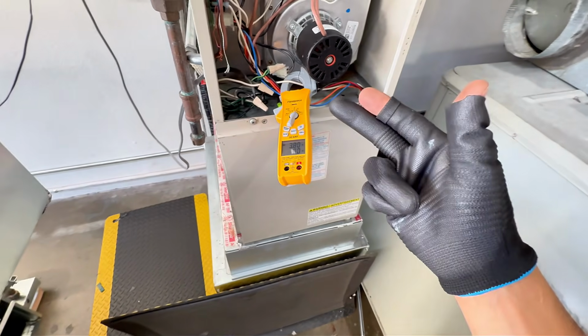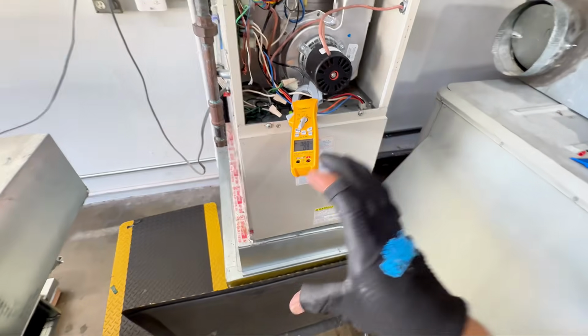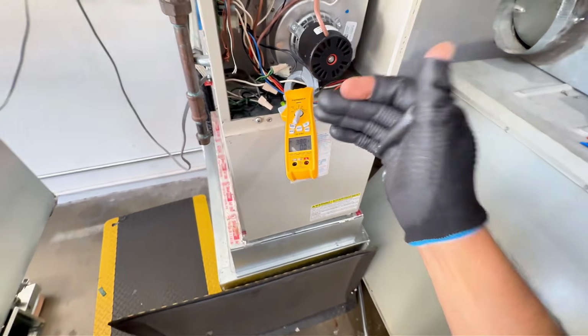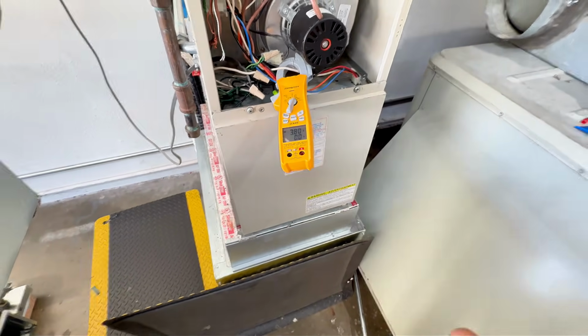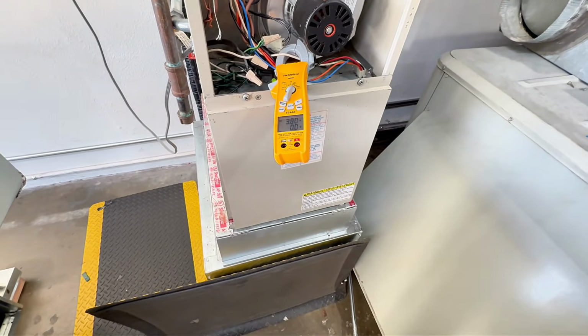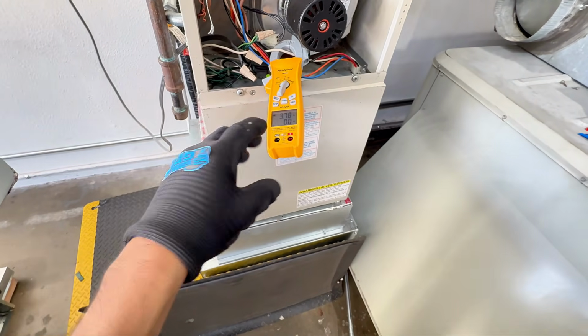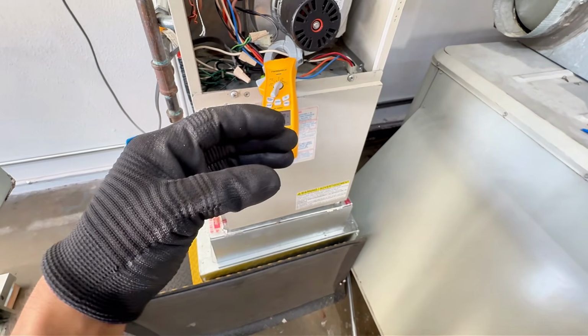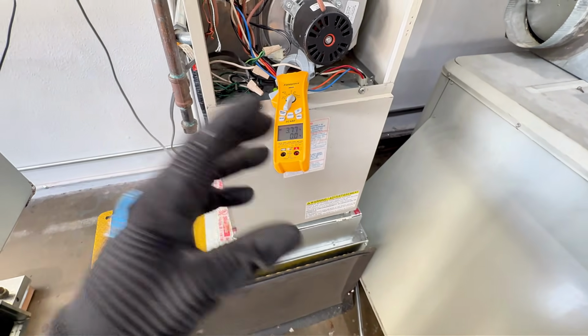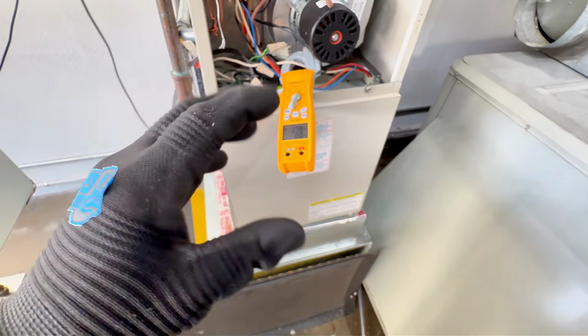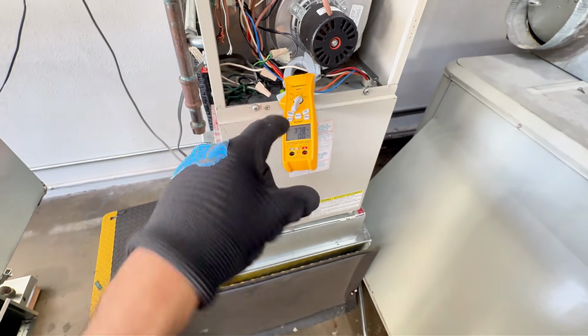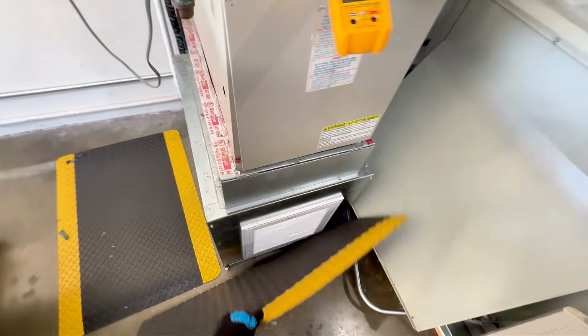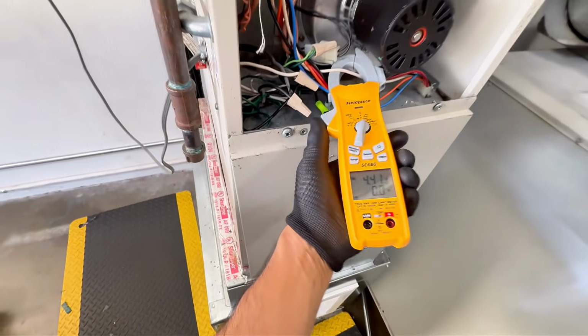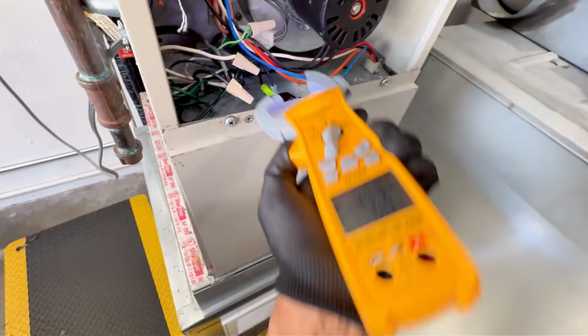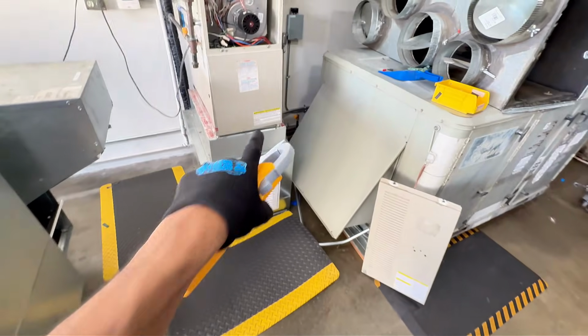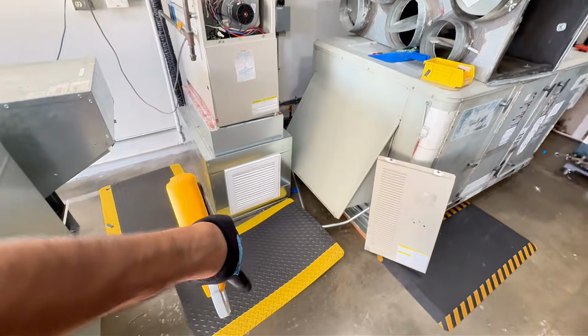So with the PSC motor, whether you have a restriction on the return or supply, your current will go down. And you might think, well, that's okay, but not really, because these motors are intended to work at a certain temperature. All that heat now is collecting in your motor, and overall, it's not good for the life expectancy of the motor. So I'm going to go ahead and let it breathe, and it went back to 4.5. Okay, so on the PSC, restriction, amps went down.